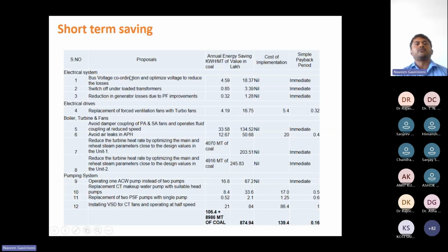Just go through that. For the electrical system: bus voltage coordination, switch off unloaded transformer. By observing the transformer loading when the load is less, we switch off one transformer, and that transformer's load will go to the other, parallel transformer. Reduce generation loss by PF improvement. PF improvement comes from increasing the size of the capacitor bank. We have a capacitor bank. We get 0.96, but it will come to 0.99 by increasing the capacitor bank.